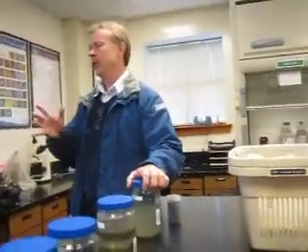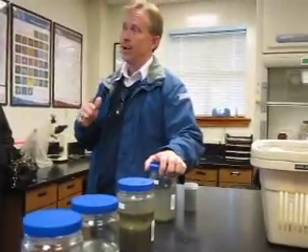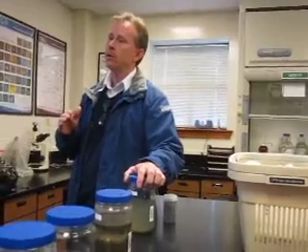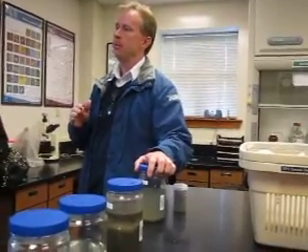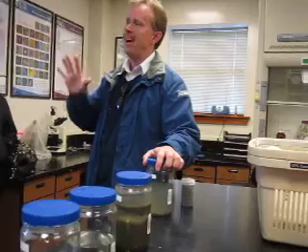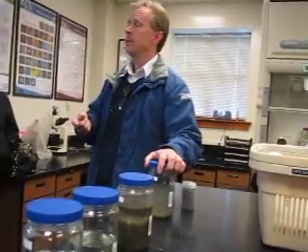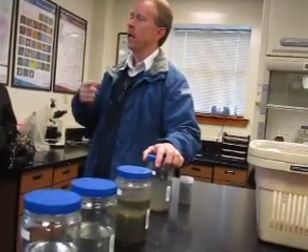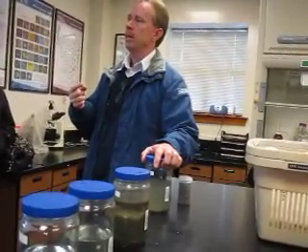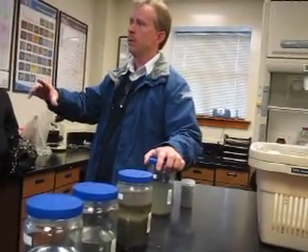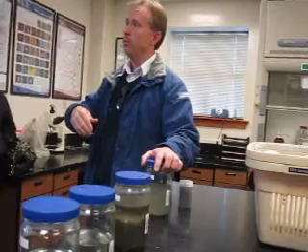Well, we're always testing what's coming in. I shouldn't say always. A lot of times we're testing what's coming in and what's going out. The permit requires us to composite sample what's coming into the plant 5 days a week. What is a composite sample for us? That means it's a flow proportional sample. We got an automatic sampling device that will collect a sample every so often. When so much flow passes by, we got it programmed to collect a sample.